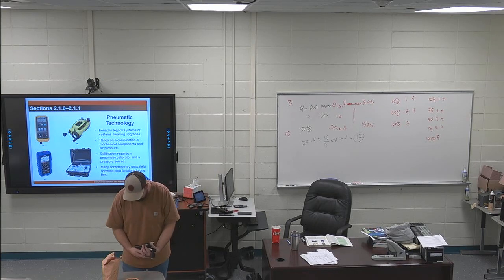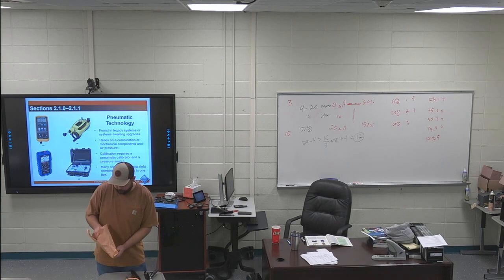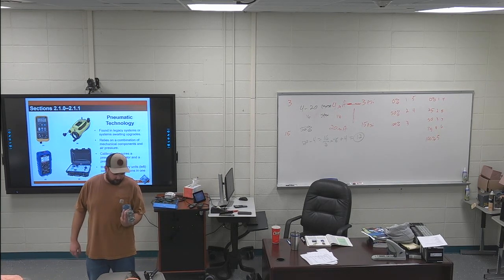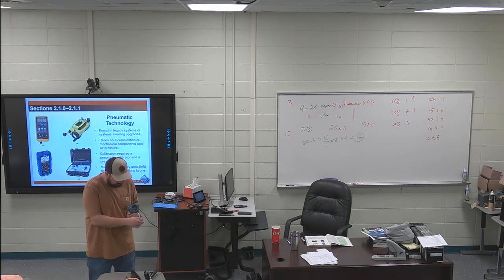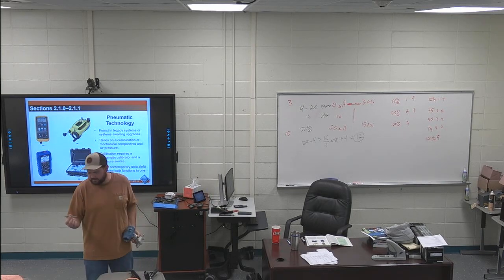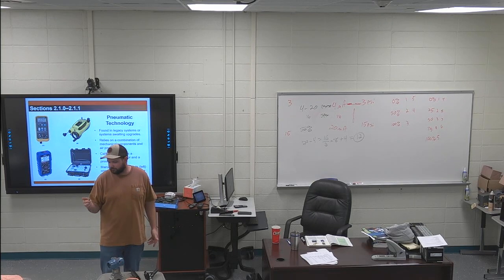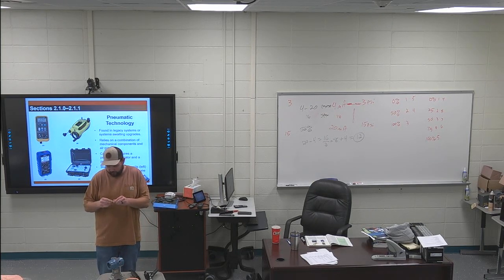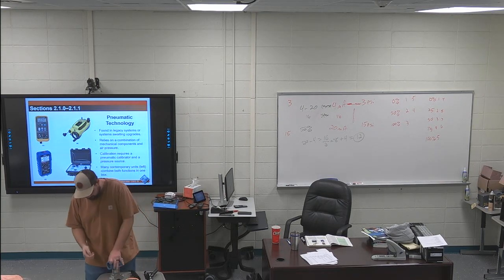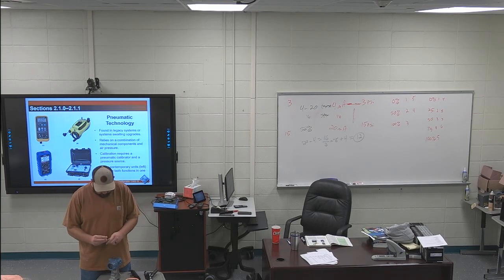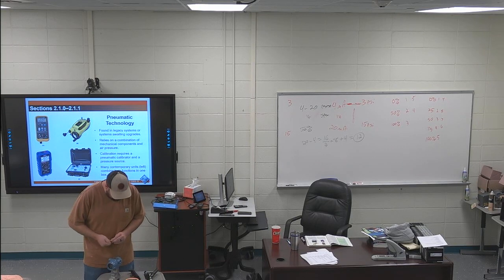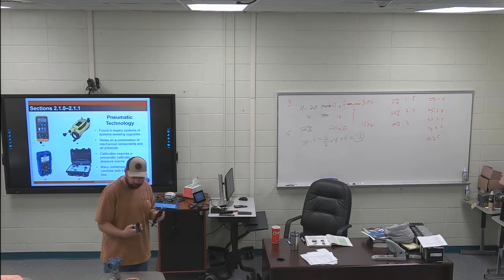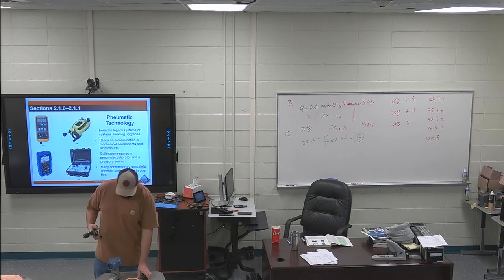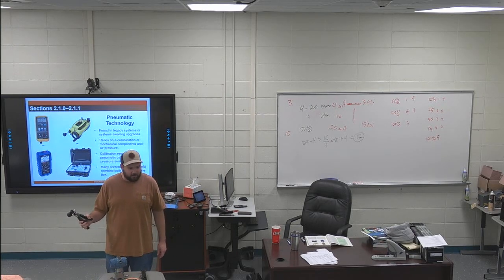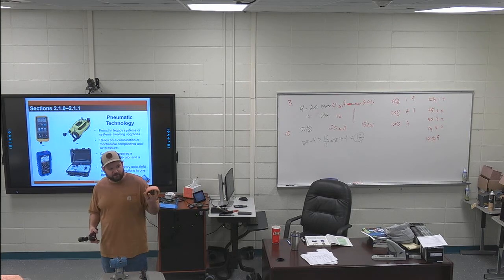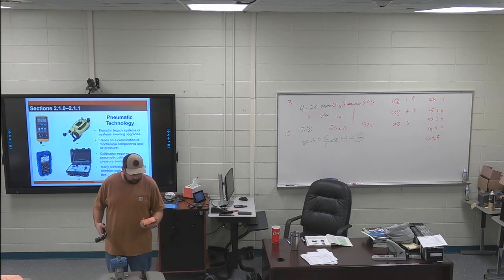So this is literally one of the pressure transducers that's going to go on that methanol plant in the back. So you've got an input and an output. They've got them screwed off right now, but you can see I could unscrew that. This is called a stinger. It's probably good to know if you're getting into instrumentation. They're just two little fittings, and I could take this off, and this is what I would unscrew and put in there. I have hoses that attach to this, or the end of this. One side of this meter is my input, and I sit there and pump it up to an exact pressure, and then I can read it on the other side of the gauge and make sure that it's reading correctly and outputting the right amount.